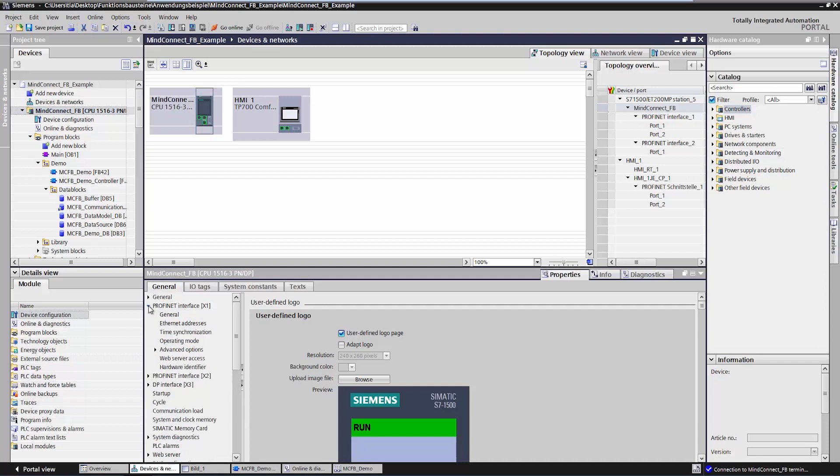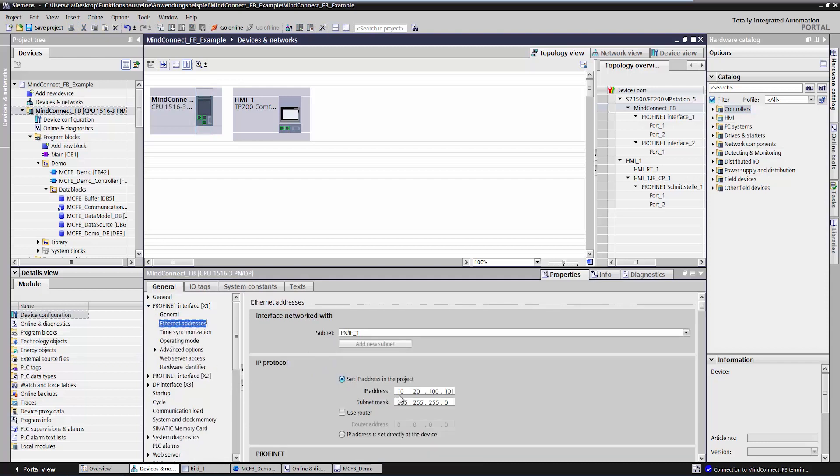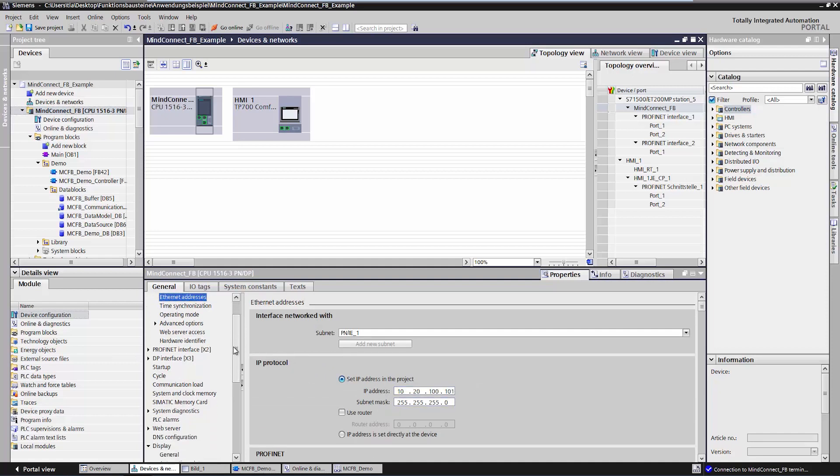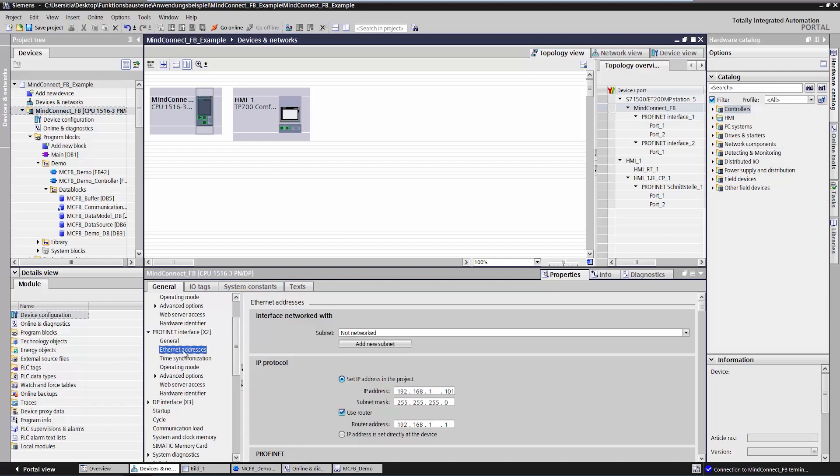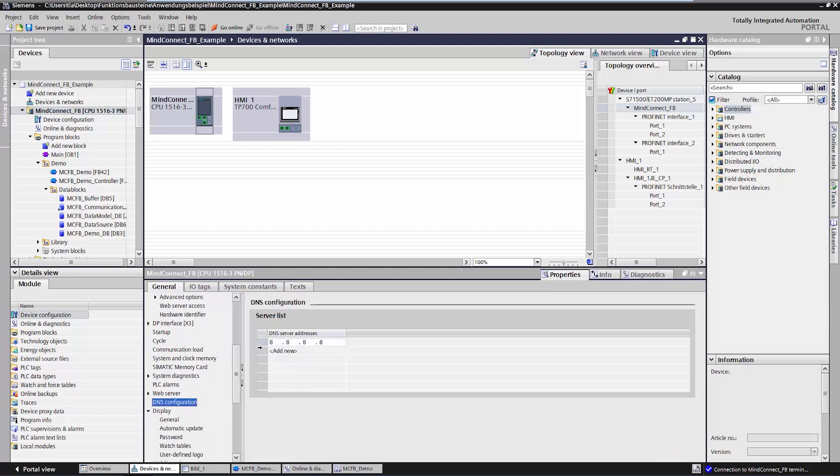The first thing I want to show you now is the settings we'll need to configure for the CPU. I assign an IP address to my CPU. In this case, the IP address will be 10, 20, 100, 101. Now I can use a Scalance M to connect my controller to the Internet and to MindSphere. Here too, an IP address must be assigned and I must specify a router which the controller will use to get online. A DNS server must also be configured. We'll use a Google server in our example.